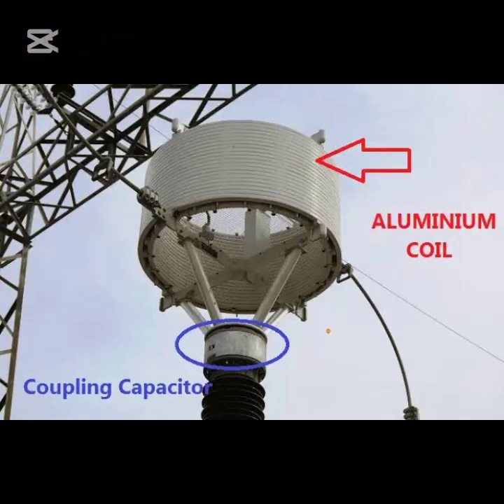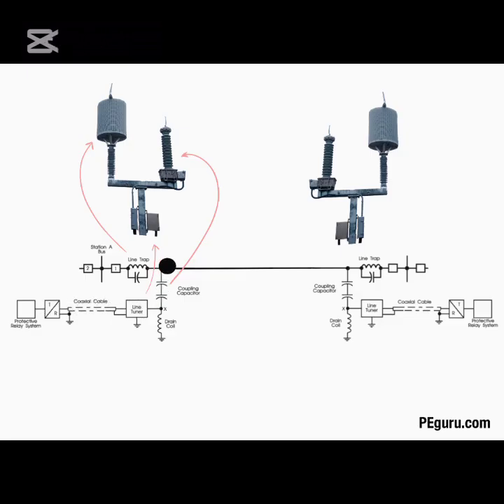2. Coupling capacitor. The function of the coupling capacitor contrasts that of the main coil. It receives high-frequency carrier signals from other substations and blocks low-frequency signals. When signal frequencies are high, the capacitor's reactance decreases, allowing for low impedance. Conversely, low-frequency signals lead to high reactance, resulting in high impedance.